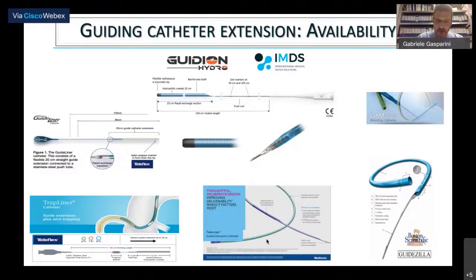So we should avoid the razor effect. For this reason, an atraumatic tip is a very important feature in this device. Then pushability. Pushability is obviously important when we have to use a device that is needed to improve the support. Pushability is very important because we have to advance it into calcified or tortuous or very distal lesions. And for the same reason, the hydrophilic coating is important, in order to improve the trackability of this device into the coronary artery vessel.